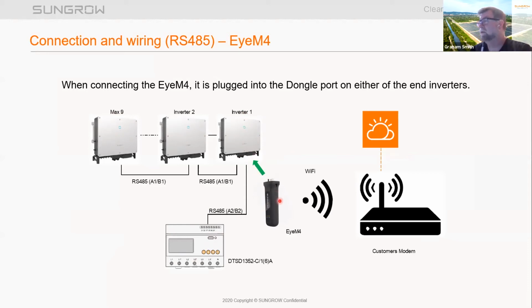And from there, the Wi-Fi signal goes to the customer's modem and up to the iSolar cloud. So yeah, just remember the meter and the dongle plugs into either inverter number 1 or number 9 if you're using the dongle. And there we see I've done the daisy chain there, which is the RS485 A1B1, which links all the inverters, and the A2B2 links the energy meter.